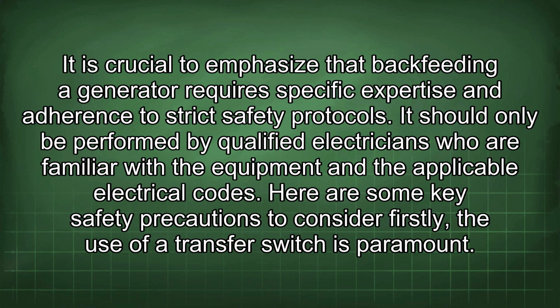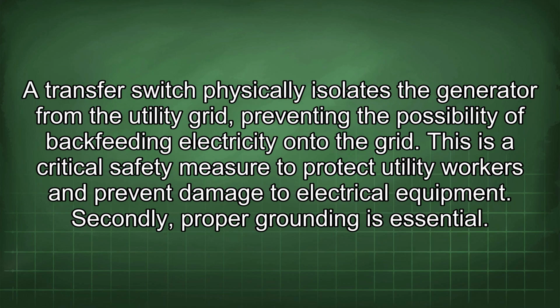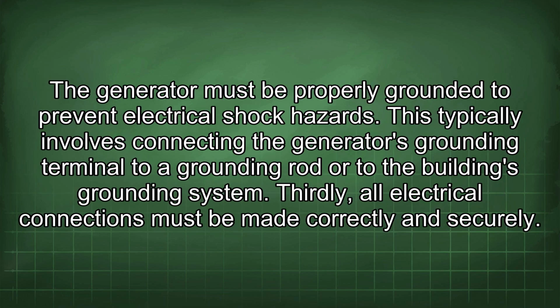Firstly, the use of a transfer switch is paramount. A transfer switch physically isolates the generator from the utility grid, preventing the possibility of backfeeding electricity onto the grid. This is a critical safety measure to protect utility workers and prevent damage to electrical equipment. Secondly, proper grounding is essential. The generator must be properly grounded to prevent electrical shock hazard. This typically involves connecting the generator's grounding terminal to a grounding rod or to the building's grounding system.